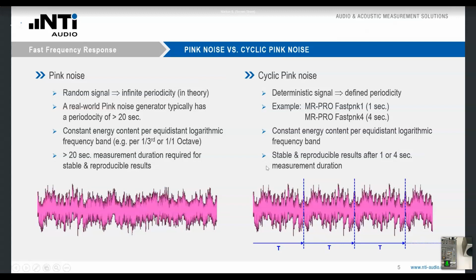If we want to measure using an ideal pink noise signal, or let's say a realistic classical pink noise signal, we need to wait typically 20 seconds or longer until we have stable and reproducible results. If we do the same with the cyclic pink noise, however, we can do it much quicker. We only need 1 or 4 seconds. So this is a key advantage of this approach.